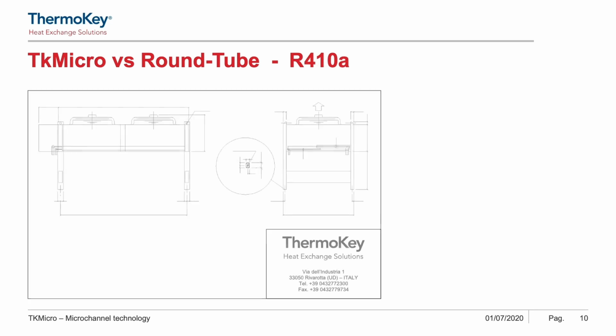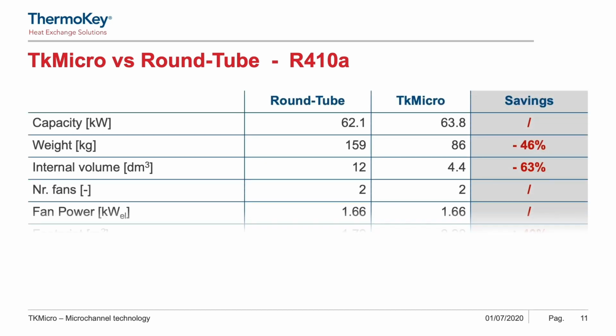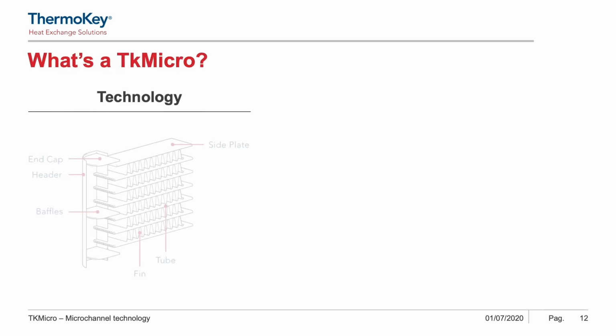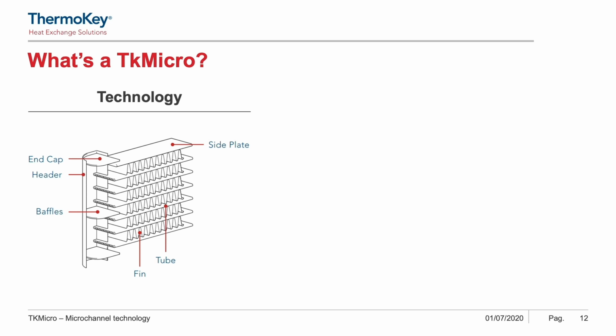In particular, about weight, we can reduce the weight up to 70%. We can reduce the internal volume down to 75%. The number of fans could be reduced by 2 pieces. The fan power could be cut by 20%, and finally, the footprint reduced by 50%. But let's focus on what is a microchannel heat exchanger.